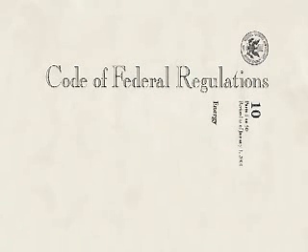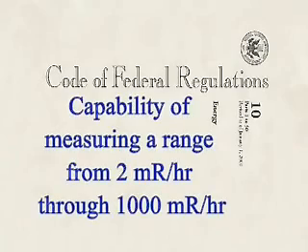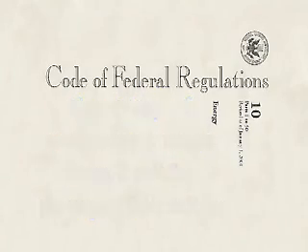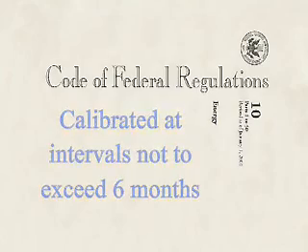Instrumentation requirements include having the capability of measuring a range from 2 mR per hour through 1,000 mR per hour. Each instrument shall be calibrated at intervals not to exceed 6 months and after servicing, except for battery changes.